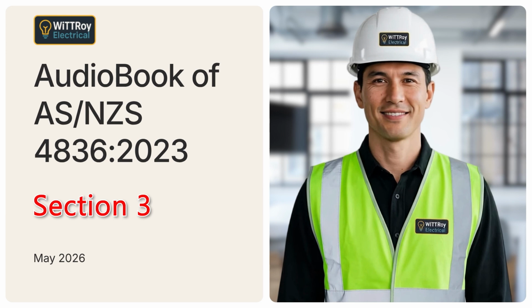3.1.4.3.4 Removal of tags. 3.1.4.3.4 explains when tags may be removed. A danger tag may only be removed with the permission of the person who signed it, or according to the approved tag removal procedure. A warning tag or out-of-service tag may only be removed by a competent person who has evidence that the plant or equipment is safe to operate. In simple terms, a tag must not be removed just because the work is urgent or because someone wants to use the equipment. A tag is removed only when it is safe and authorized.